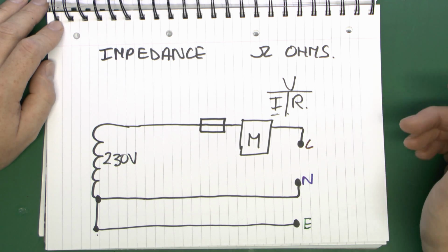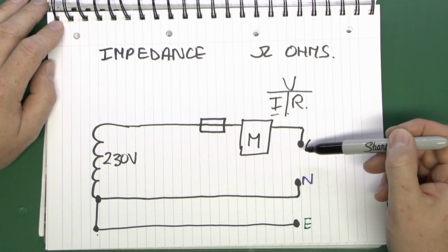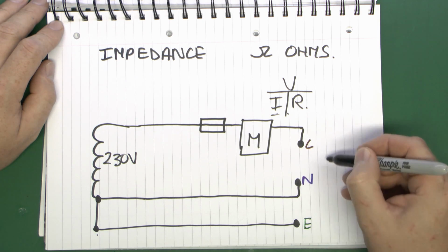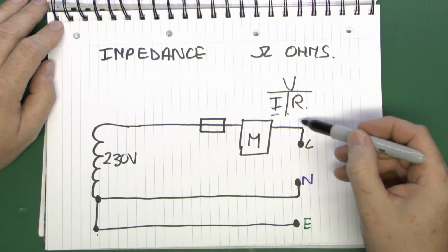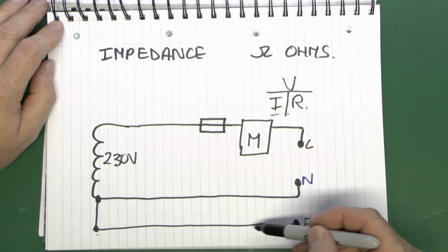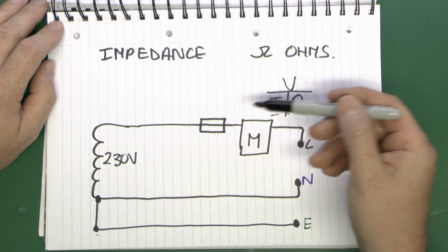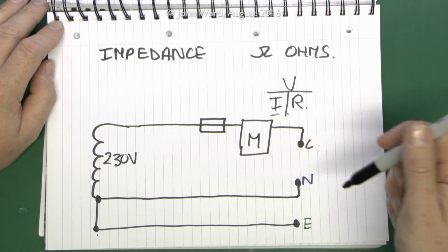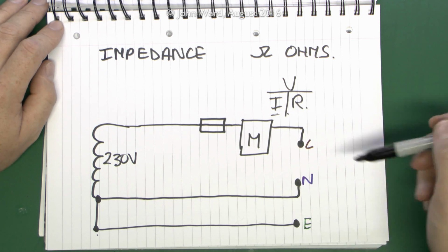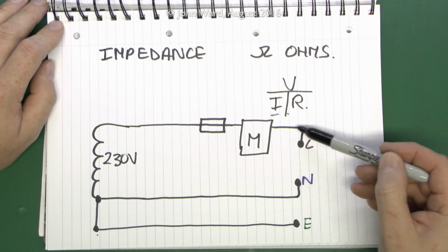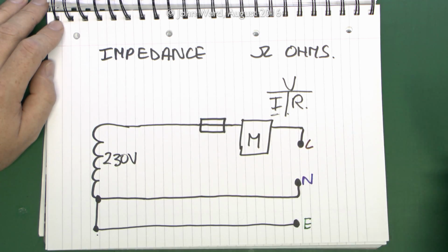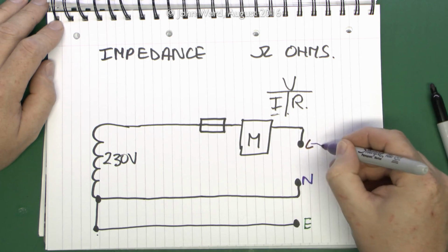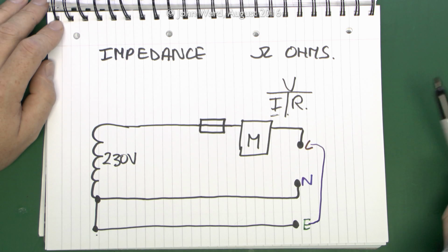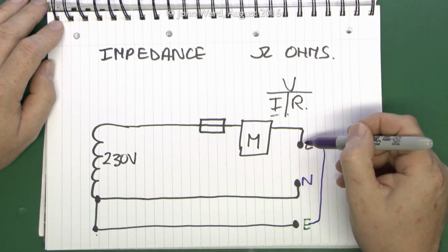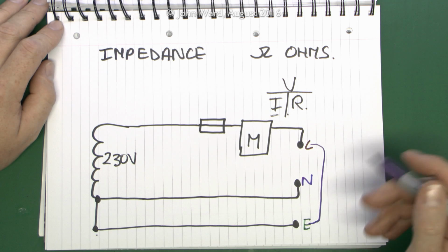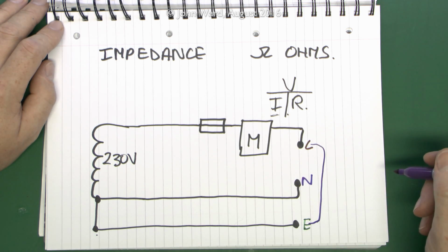Now, when we talk about the loop impedance, what we're talking about is a loop through wherever a fault occurs. So there might be, say, a fault here between line and earth, and then it's the entire loop of the whole circuit here involving the transformer and any kind of wiring, the fuse, electricity meter, and then if it was inside the building, the circuit wiring and everything else. And the question then is how much current will actually flow through all of this in the event that these two wires here are shorted together due to a fault. Now, normally, of course, you wouldn't be doing this, but if some kind of problem occurred, then this is what is actually going to be happening.